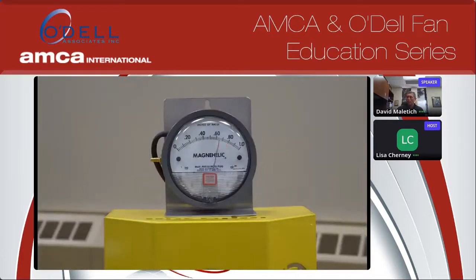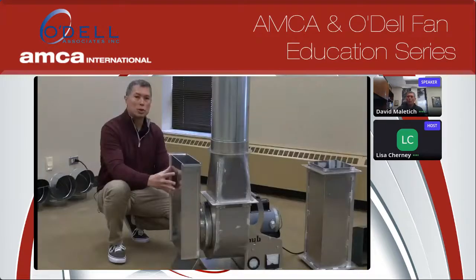Okay. Notice that the fan's doing a couple different things. One is efficiency, or the amount of pressure that the fan's generating, went down significantly. It's almost half as much as what it was originally. Second thing you'll notice is that that needle is not very stable. It's going up and down. This inlet box has actually put the fan into a surge condition. And those surge conditions on a small fan are pretty bad in that, one, it creates a lot of noise. It goes up and down.